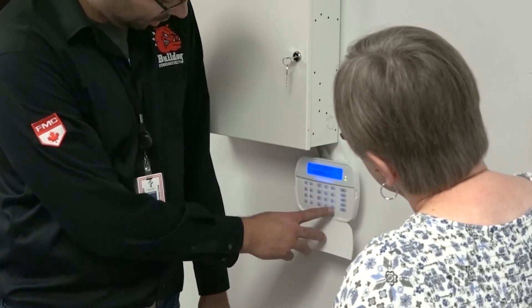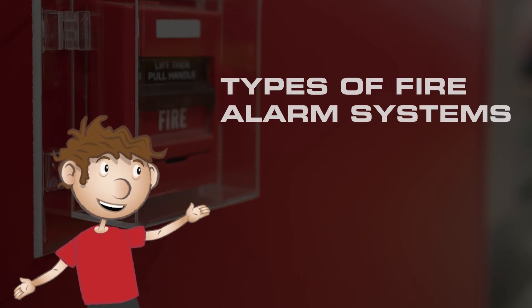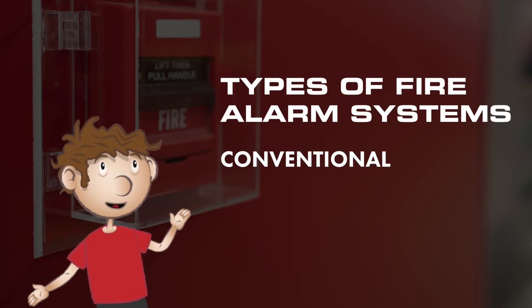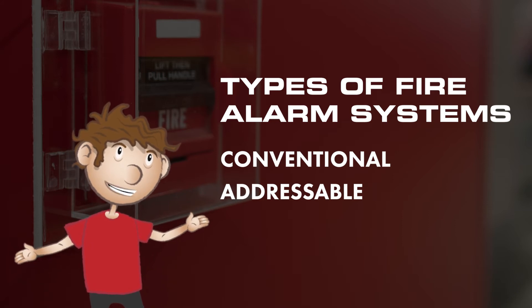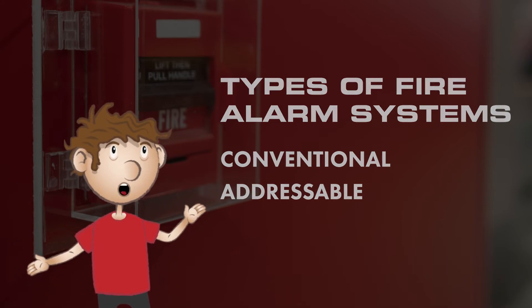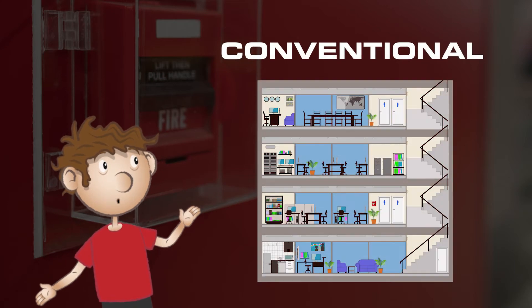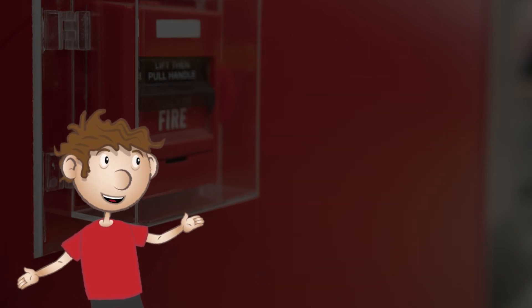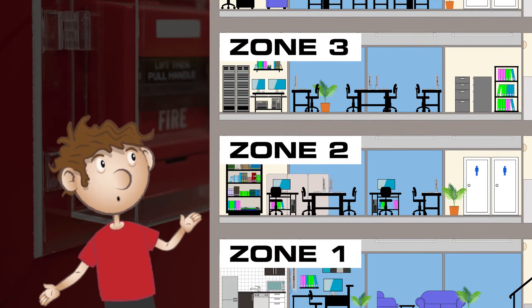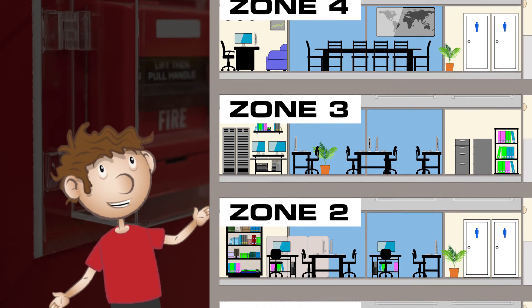Now let's take a look at the different types of fire alarm systems. There are two primary types: conventional and addressable. While both interact with devices and other components in a similar fashion, they differ in how they're connected. A conventional fire alarm system connects the control panel with each device on a separate wire and is typically set up in zones. This way, when a device is activated, the system can identify the zone and help narrow down the location of a potential fire.